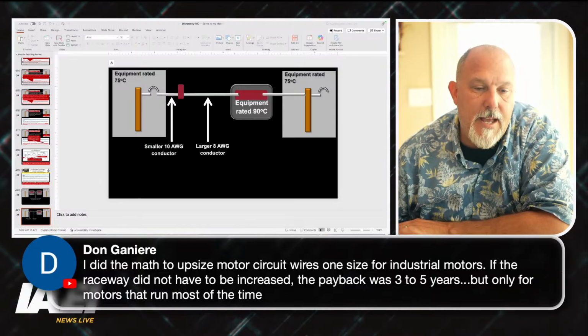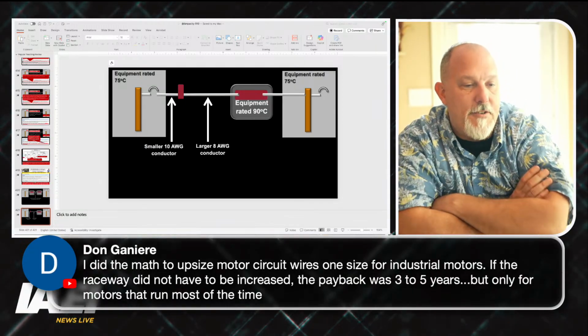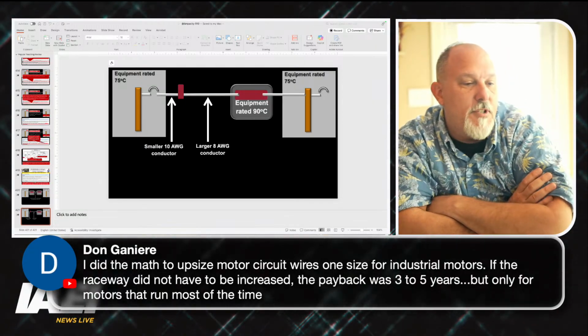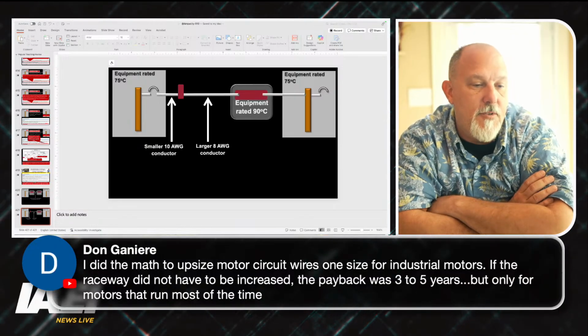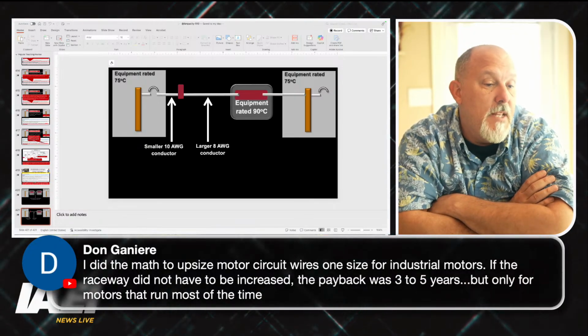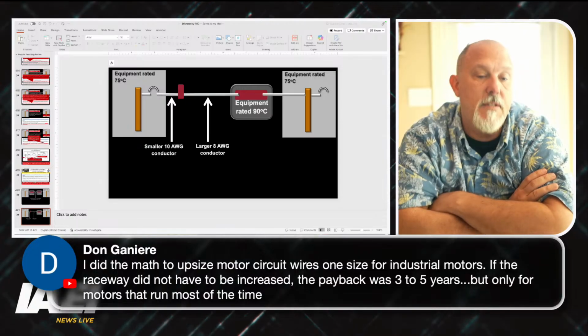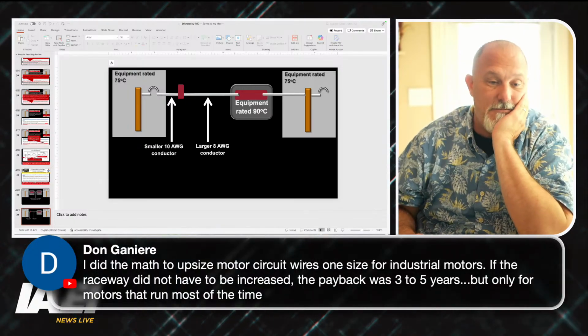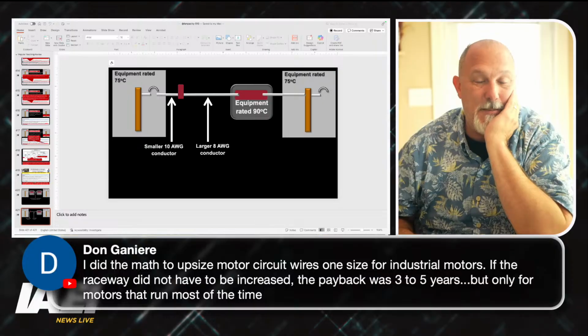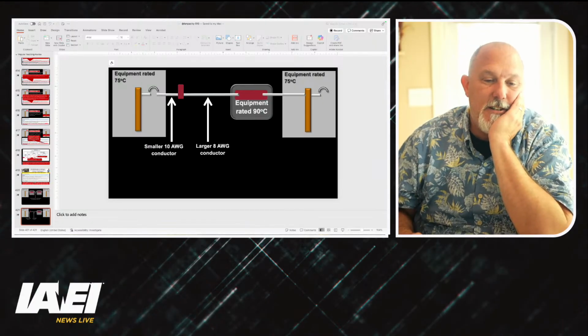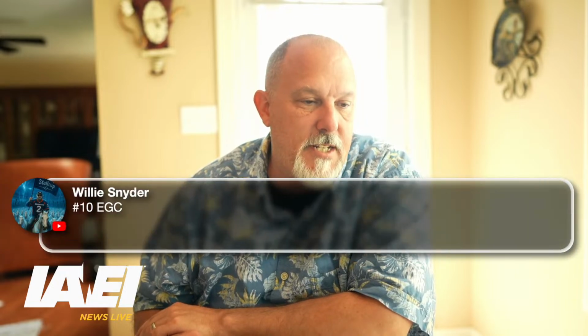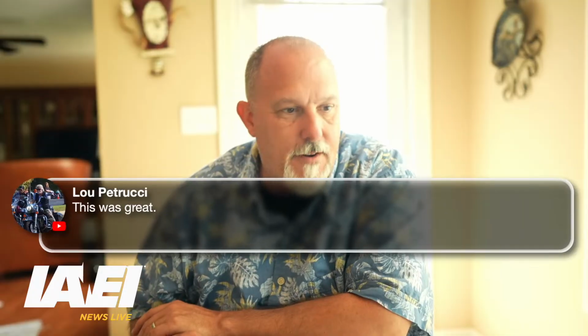Anyway, I did the math. To upsize motor circuit wires one size for industrial motors, if the raceway did not have to be increased, the payback was 3 to 5 years, but only for motors that run most of the time. Good. Thank you, Dawn. I knew you would do the math. I knew you did that. And Willie is saying a number 10 EGC. And Lou, thank you very much, Lou.